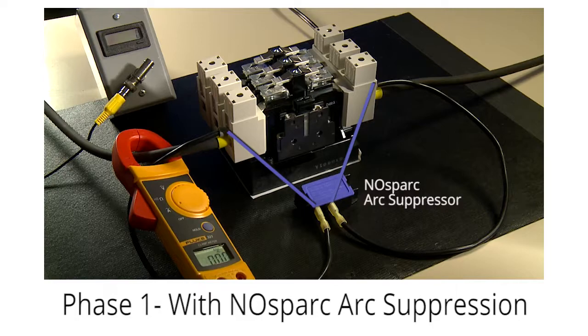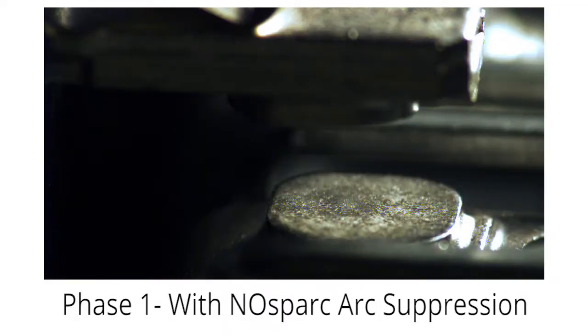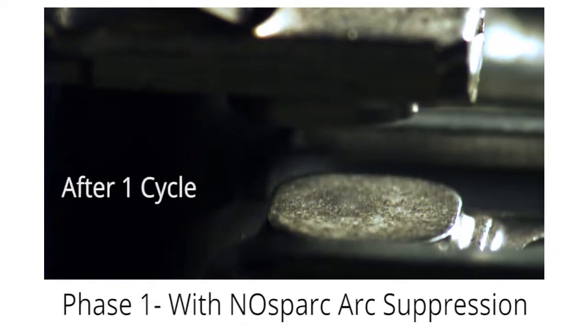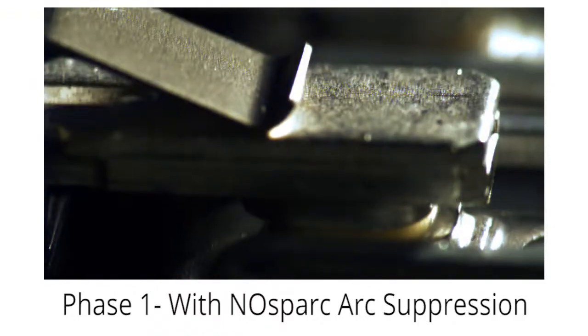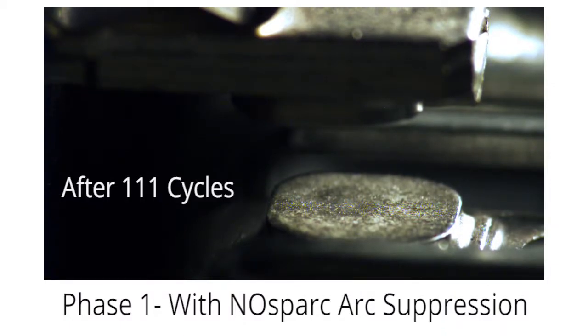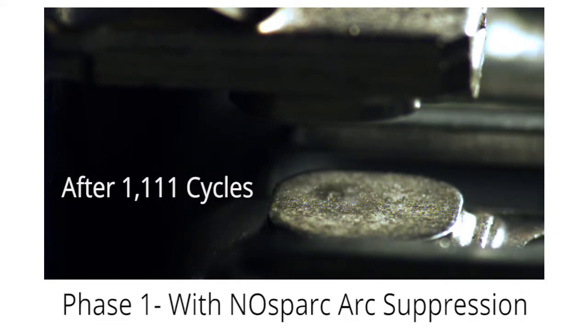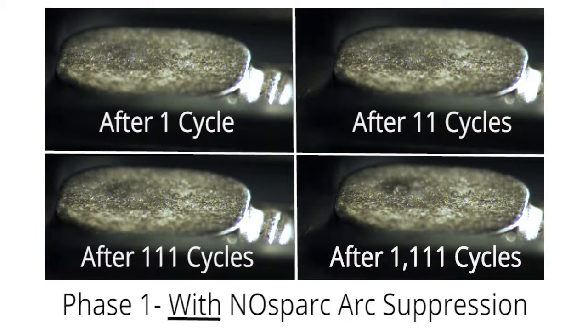In phase one, we connected our single-phase NOsparc arc suppressor across one leg of the power contactor, then connected the arc welder directly into the same leg. We set the arc welder at 235 amps — the maximum allowable current rating of our NOsparc arc suppressor. We then set up our high-speed camera and ran the contactor through the following contact cycles: 1 cycle, plus 10 additional cycles, plus 100 additional cycles, plus 1,000 additional cycles, for a total of 1,111 cycles — all of them suppressed by a NOsparc arc suppressor.